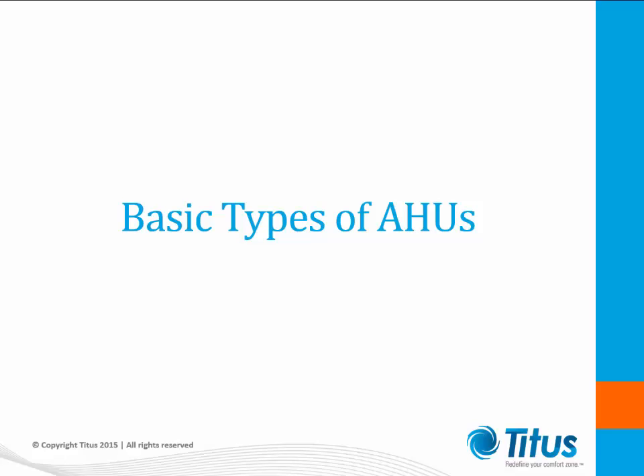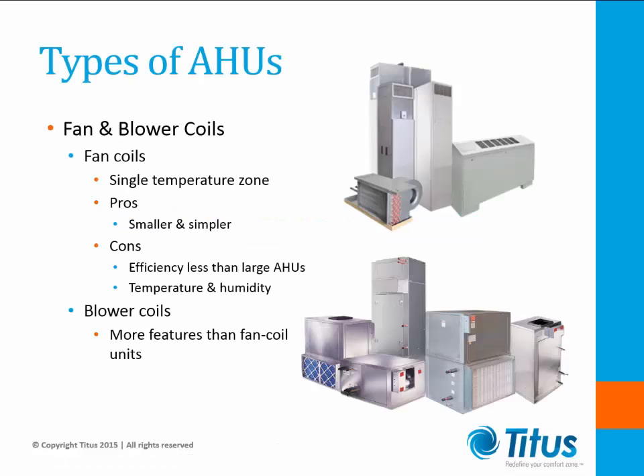We're going to take a bit here and just look at the basic types of AHUs. To start, we're going to look at fan and blower coils. When we look at a fan and blower coil, they generally consist of a fan and a heat transfer coil. Simple filter combinations may be incorporated to keep coils clean, as well as removing particulate from the air. Fan coils generally have simple controls and serve as a single temperature zone. They tend to be less efficient than larger AHUs and have difficulty holding tighter temperature and humidity control. The typical differences between a blower coil and a fan coil may consist of filter options in 2 and 4 inch thicknesses, larger coil offerings, electric heat, and possible damper options.